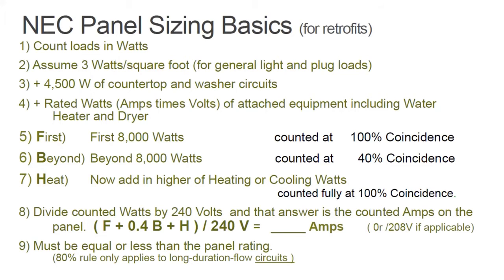What the National Electric Code looks at in panel sizing is written in a complex format, so I tried to simplify it here. The basic issue is you count the load in watts, and they assume 3 watts per square foot of conditioned space for general light and plug loads - all kinds of portable devices like lamps and other things - plus another 4,500 watts of circuits defined in the code: two countertop circuits in the kitchen for countertop cooking, and a washing machine or laundry circuit.